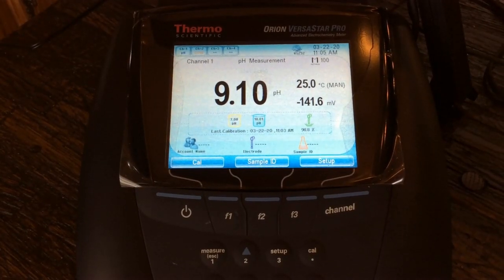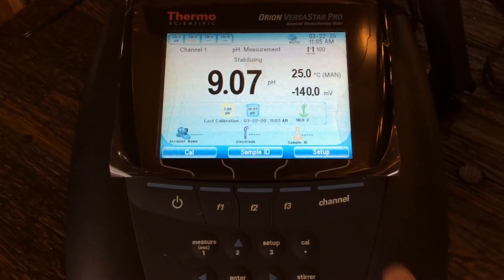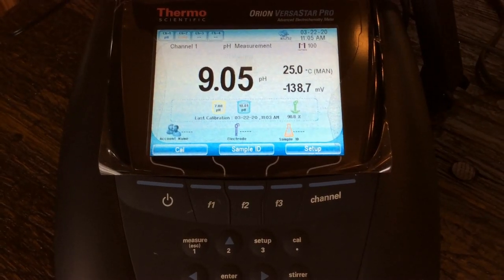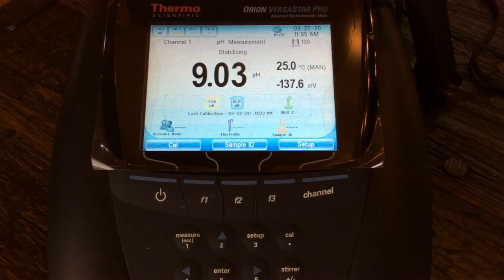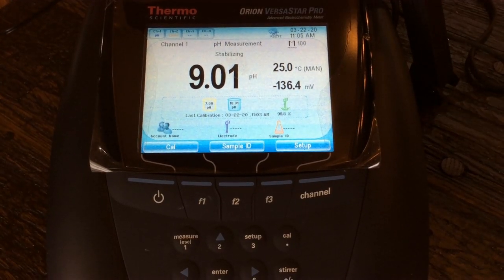One of the cool features I like about this VersaStar Pro is on this pH reading, it saves your last calibration point. So we can see the date — 3/22/20 at 11:03 AM — and see what our slope was: 98.8. That's a really nice function if you need to make sure that it has been calibrated to meet your standards. The VersaStar Pro Benchtop Meter gives you the flexibility to customize it however you need for whatever readings you need in your lab. If you have any other questions, please let me know, and thank you for watching the demonstration.